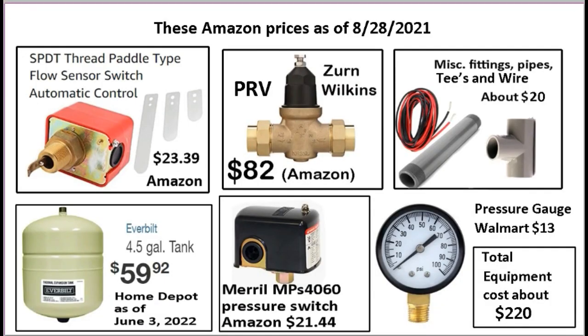Okay, in this picture I'm going to show you some of the equipment that you will be using, or that we can use to find better solutions to the cycle stop valve. So this is the equipment I'll be showing you in my 4 solutions to improving a cycle stop valve. This is called a paddle flow detector, and you can install this in your system to detect when there's water flow, and this is very useful in some certain circumstances. This is a pressure reducing valve. It's similar to a cycle stop valve, except it doesn't have the internal leak. It only costs $80 for a high quality pressure reducing valve.